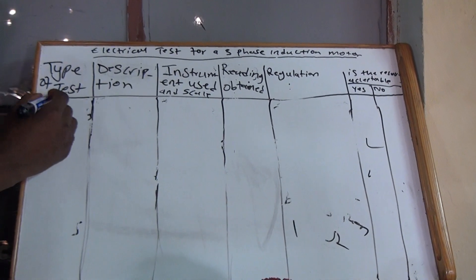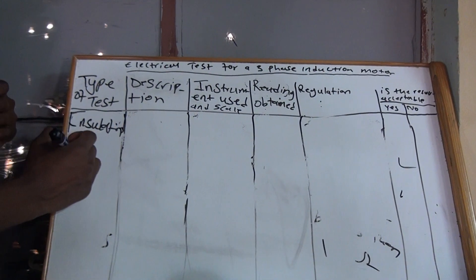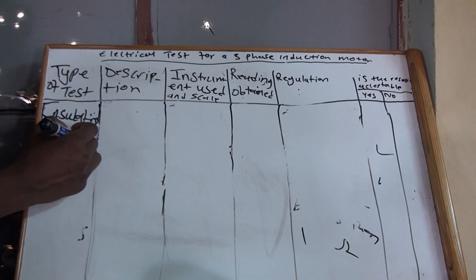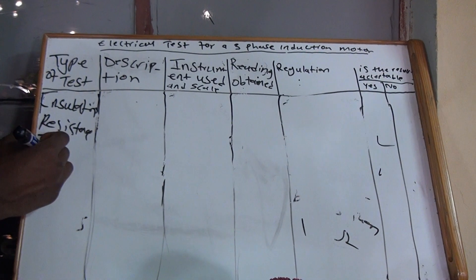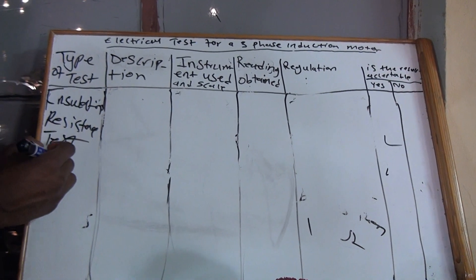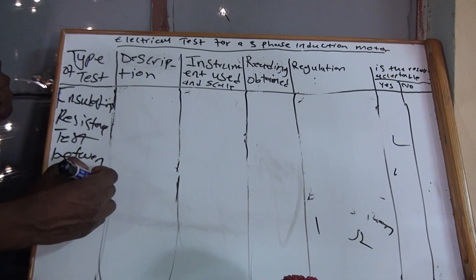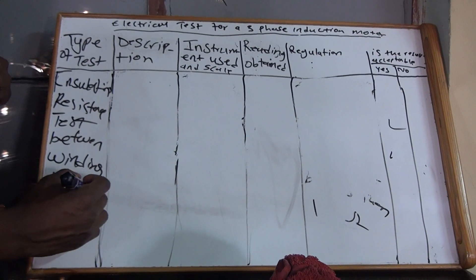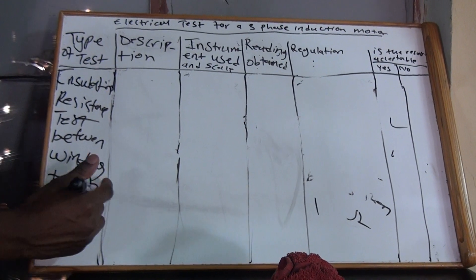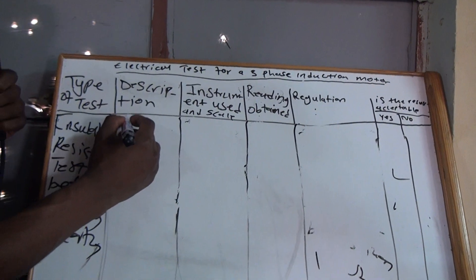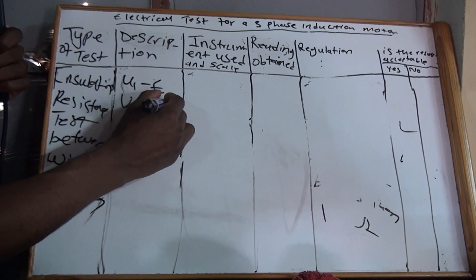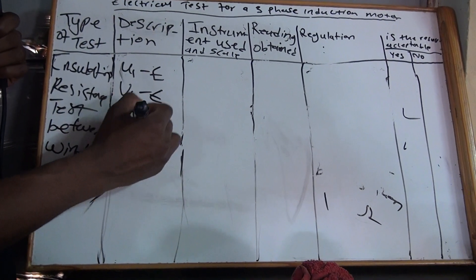The last test is the insulation resistance test between windings and the frame (E). On the description you'll write U1 and E, V1 and E, and W1 and E.